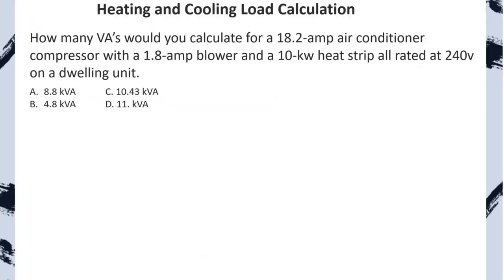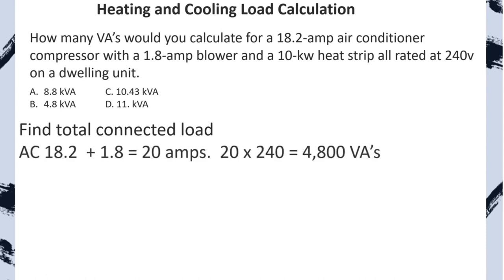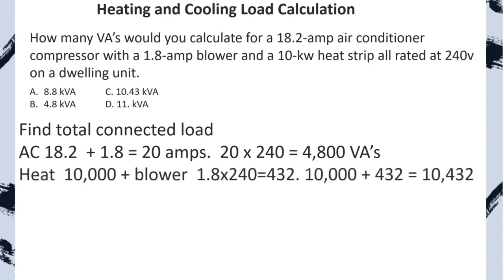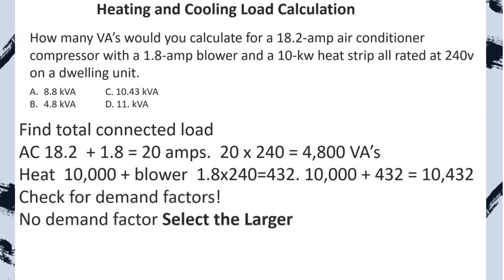Practice problem: How many VAs for an 18.2-amp air conditioner compressor with a 1.8-amp blower and a 10 KW heat strip, all rated 240V, on a dwelling unit? First, total connected load for AC: 18.2 plus 1.8 equals 20 amps, multiplied by 240V equals 4,800 VAs. For heat: 10,000 VA plus the blower motor (1.8 amps multiplied by 240V equals 432 VAs) for a total of 10,432. Check for demand factors: none. Select the larger of the two — the heat. We select C.